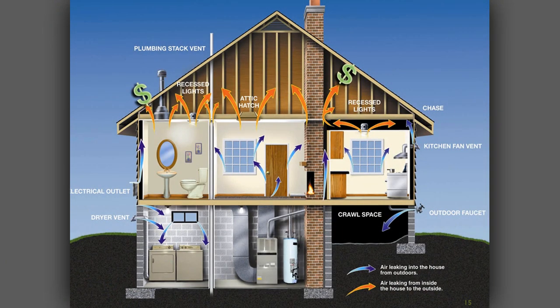If we go in the basement and we smoke where the plumbing is, because a lot of times you can see that hole where it's coming out, then if the smoke's going up, it's leaky. Well, that tells you it's leaky at the bottom, because the blower door is in the door at the front of the house. It could be pulling up from the bottom and out. But does that tell you that it's leaky from the top? We don't know. And that's one of the things with zonal diagnostics: it tells us that the wall is leaky. We then have to determine whether it's the top or the bottom too. So you need to look in both locations.